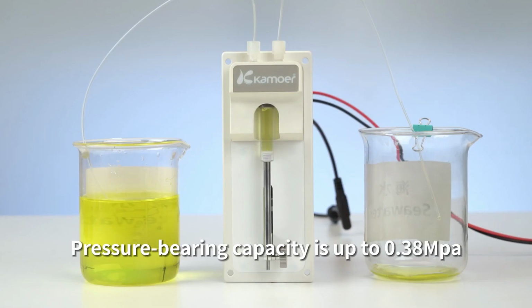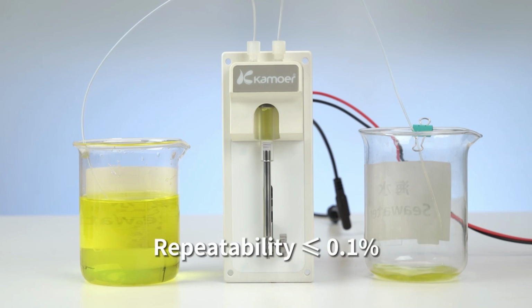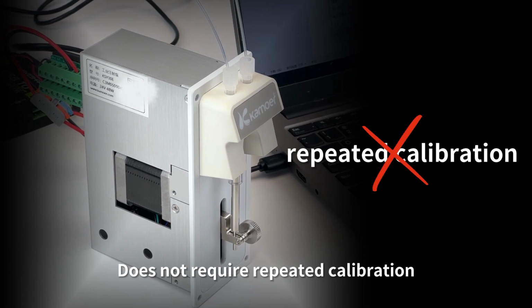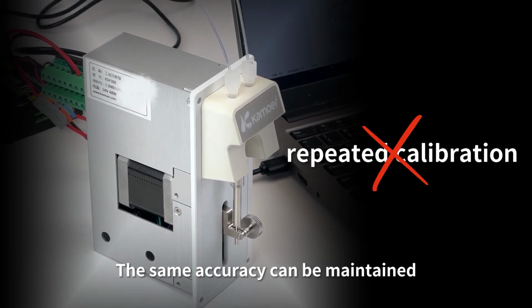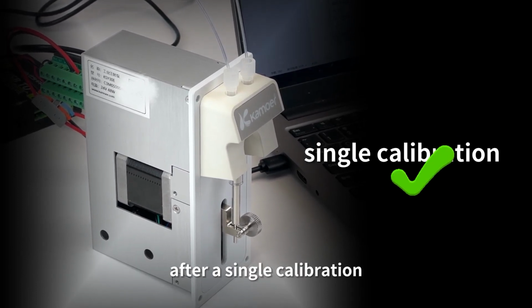Compared with the peristaltic pump, KSY30E has more pressure and higher precision. Pressure bearing capacity is up to 0.38 MPa, repeatability ≤ 0.1%. It does not require repeated calibration. The same accuracy can be maintained after a single calibration.